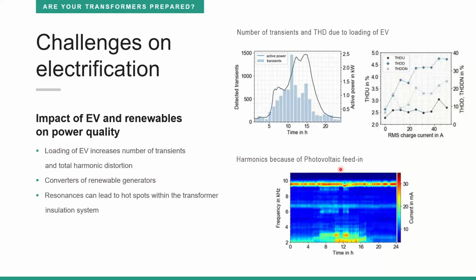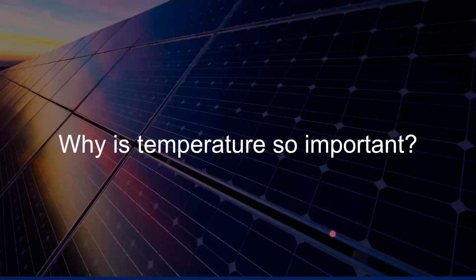Photovoltaic feed-in also causes harmonics, which is shown in the lower graph. So during noon, where we have a strong photovoltaic feed-in, we have also quite high harmonics. And these harmonics and resonances can lead to hotspots within the transformer insulation system. So overall, we can say we have a higher loading, which brings also higher temperatures to the transformers. This, of course, raises the question, why is temperature so important for the transformer? And I want to give this question to Peter, who wants to show us some slides in that respect.